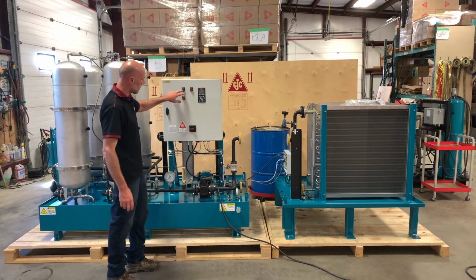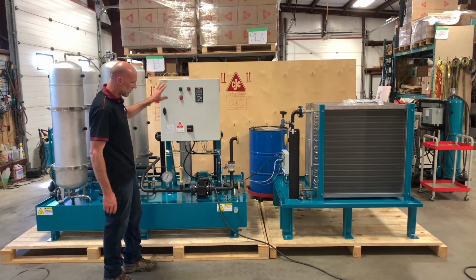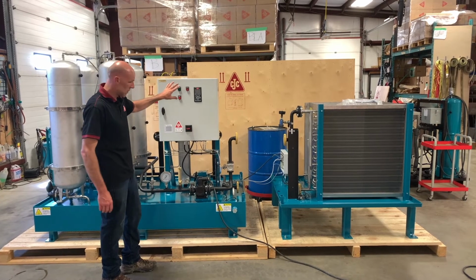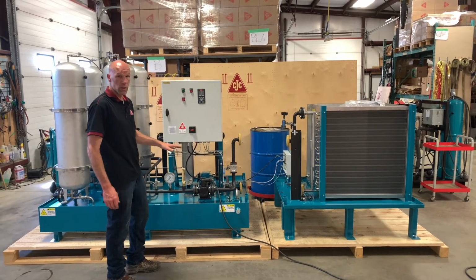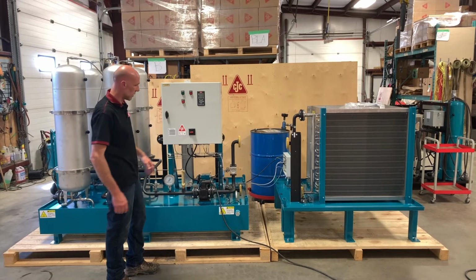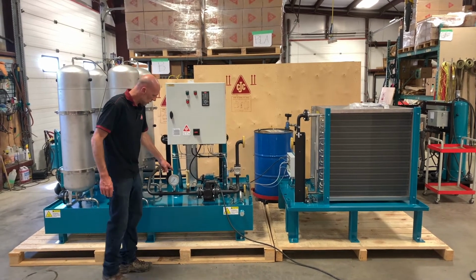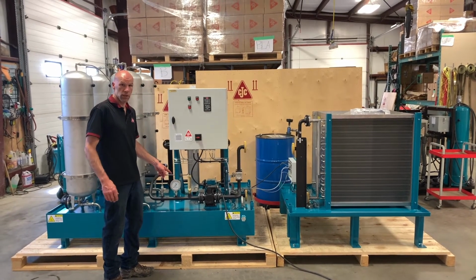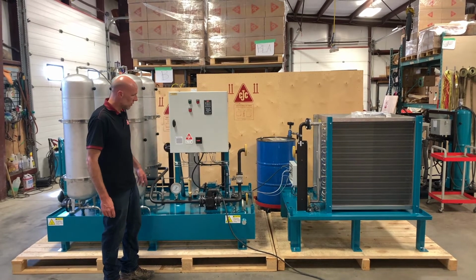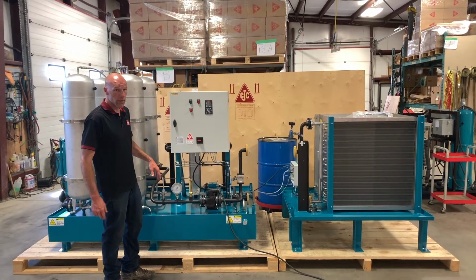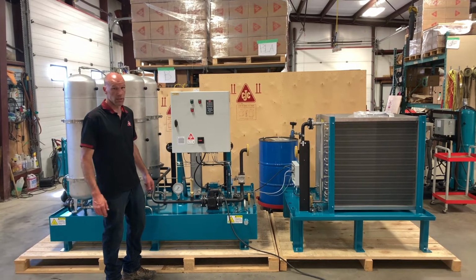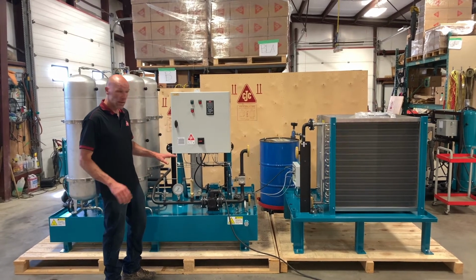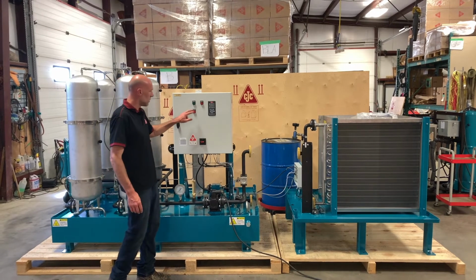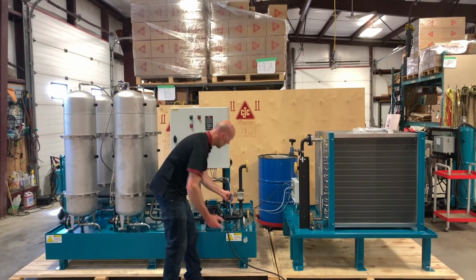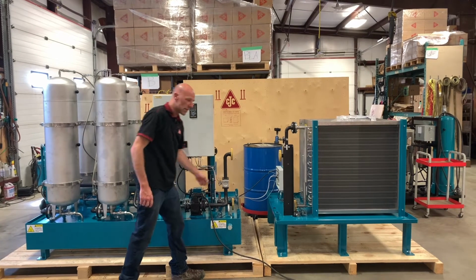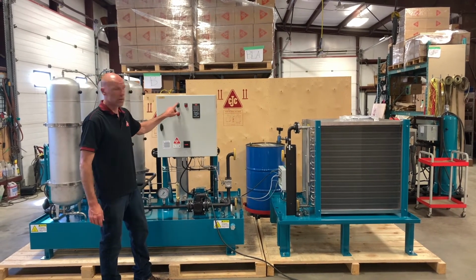Now you can start the unit, and we recommend staying close and monitoring to make sure that once you get the oil out of the drain tank, you're not going to walk away and forget about it. So you'll either see the pressure gauge start to waver as it picks up air, at which point you can stop it, or if it's not a noisy environment, you may hear it on the pump before the pressure gauge even starts to show. Once you see evidence of air in the system, you can stop it, and then switch your valve back over to the main system, and now you can resume operation.